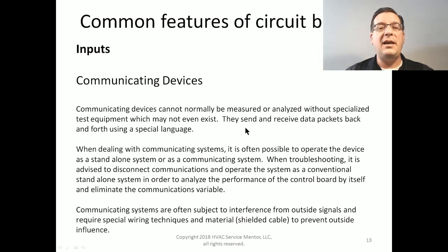These communicating devices send and receive data packets back and forth using a special language. And when you're dealing with communicating systems, it's often possible to operate the device as a standalone system or as a communicating system. All of our communicating residential equipment has this ability. You can either install a communicating controller to run it, or you can install a conventional thermostat to run it. This is a great thing to know in your back pocket, because when you're dealing with communicating systems, how do you know, is it communicating? And if it is communicating, where's the problem? Is the problem in the communication being inappropriate, or is the control board inappropriate? And if it's a control board, which one? It's really hard to figure that out.